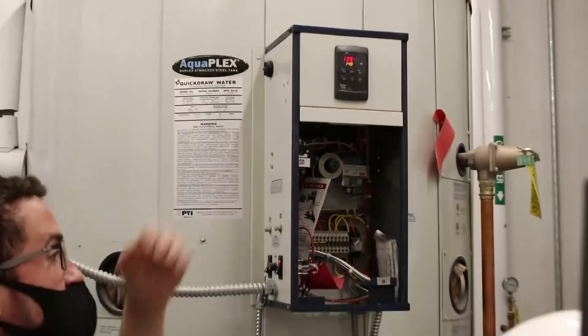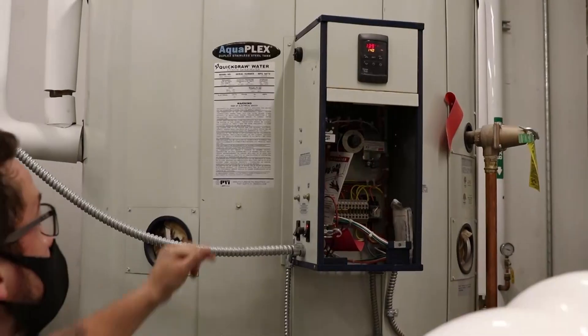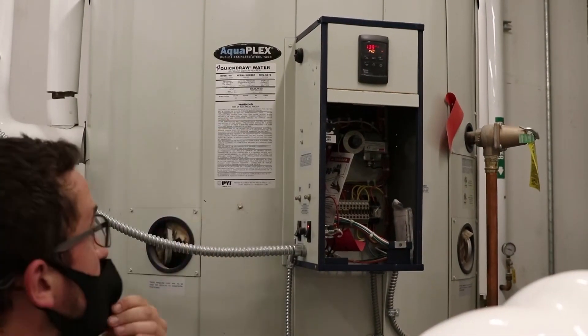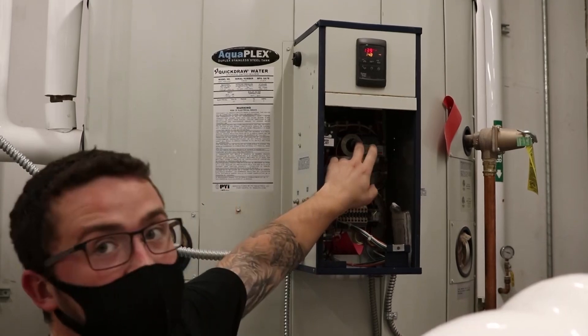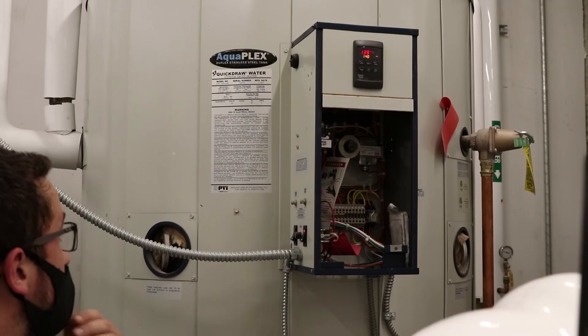So it acts as an automatic resetting high limit. It will limit the temperature at the top of the tank to whatever temperature you set the dial to. And again, that should be 10 degrees higher than the operating set point.